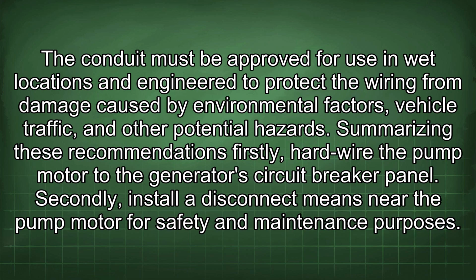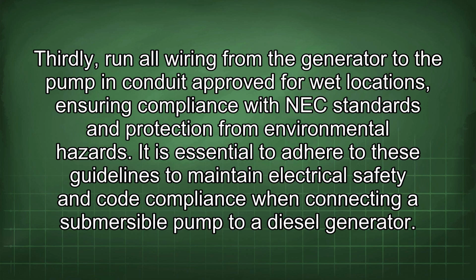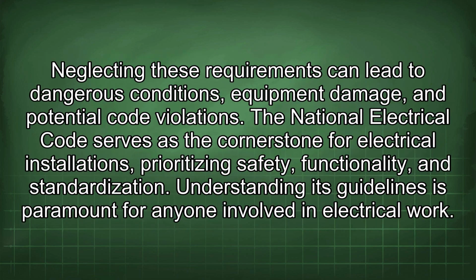Summarizing these recommendations: firstly, hardwire the pump motor to the generator's circuit breaker panel. Secondly, install a disconnect means near the pump motor for safety and maintenance purposes. Thirdly, run all wiring from the generator to the pump in conduit approved for wet locations, ensuring compliance with NEC standards and protection from environmental hazards. It is essential to adhere to these guidelines to maintain electrical safety and code compliance when connecting a submersible pump to a diesel generator. Neglecting these requirements can lead to dangerous conditions, equipment damage, and potential code violations.